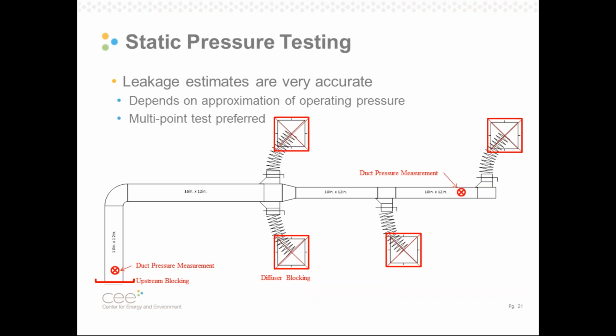So a static pressure test, it's pretty simple. I'll go through that really quick. We basically shut off an air handler and isolate a piece of ductwork. This is a cartoon here of a schematic of maybe a downstream branch of a VAV box. We block the upstream portion of this section at the VAV like reheat coil. We put in some duct pressure measurements in that system. We block the outlets. In this case, it's the diffusers. And then we take a calibrated fan and we connect it to this duct system. We then blow air in this duct system. Since we've blocked it all off, air can only escape out the leaks, and we simply record what the flow rate is on our fan at the pressure of the ducts. That gives us a very good estimate of what the duct leakage is at that operating pressure.